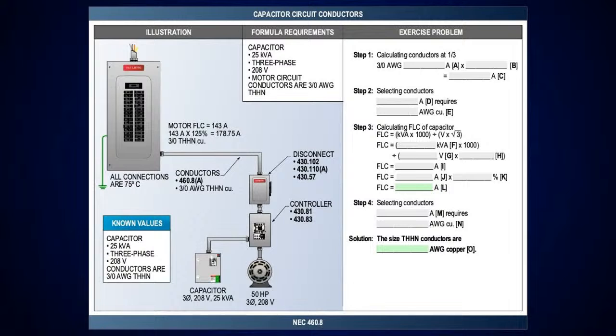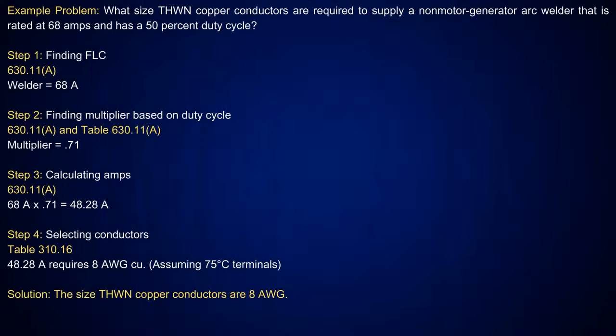You're going to do it based on calculating the conductors at a third and then calculating the full load current of the capacitor. And whichever is the largest between the two, that's the size, in this case, THHN copper conductors you're going to use. Okay? So I think that'd be a really good one there because a lot of people don't deal with capacitors much. And then 100%. The next thing we're going to get into is looking at non-motor generator arc welders, motor generator arc welders, and also resistance welders.